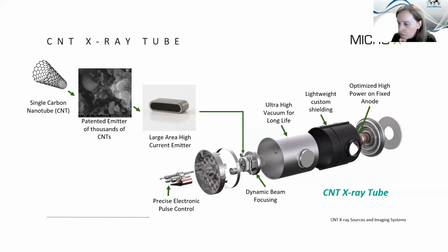People are asking, is it correct that the nanotube cannot withstand the forces in a rotating X-ray tube? No, it can completely withstand the rotation. The only reason we don't do rotation is because everything we're trying to do is about simplicity and cost effectiveness. We manage the heat by altering the focal spot size for this application, and we can get quite high, up to 100 milliamp current using that.